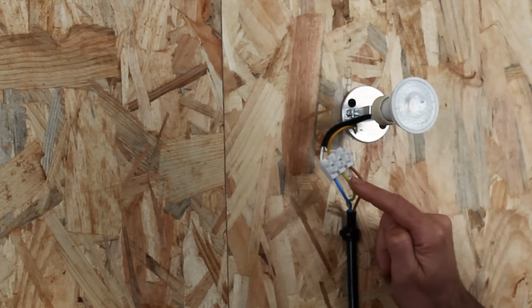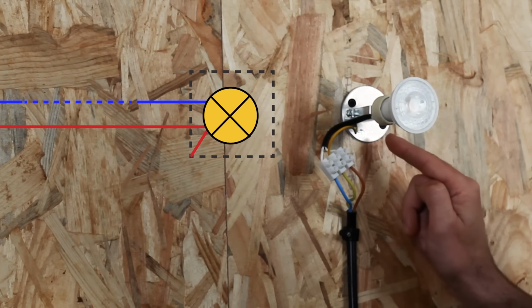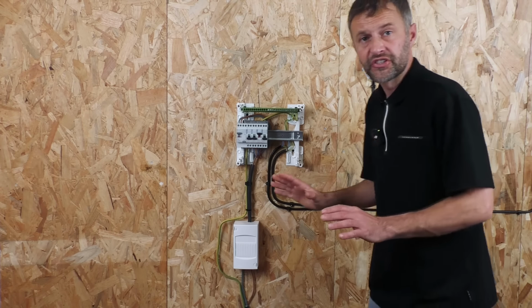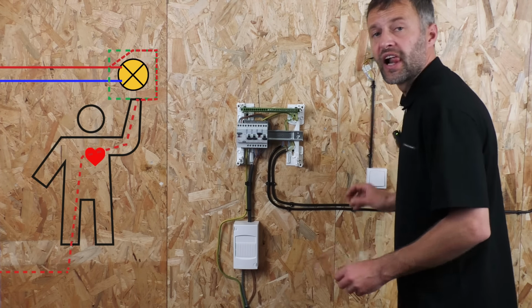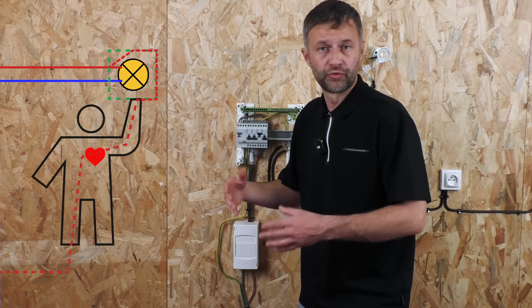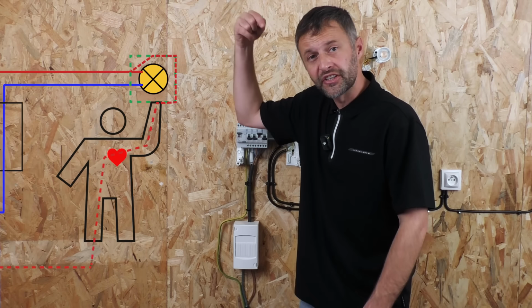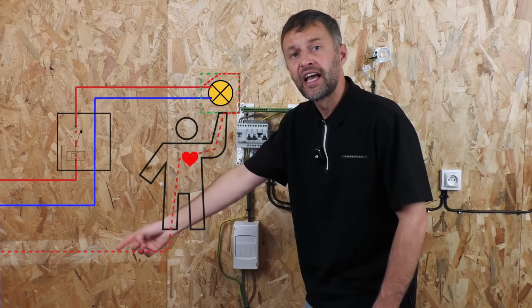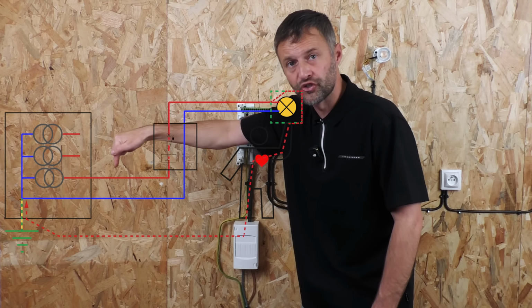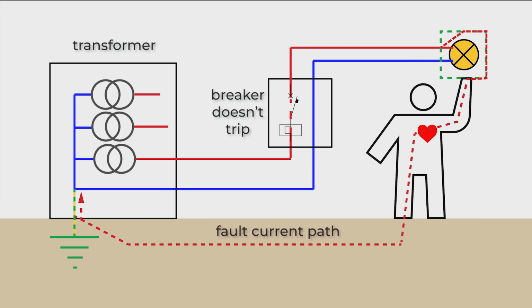If the earth wire is not connected to the metal housing and a live wire accidentally touches it, nothing may happen at first until you touch the metal yourself. And if you're standing on a wet floor or outside barefoot or wearing poor footwear, now this fault current can travel through you, through the soil and back to neutral at the transformer side, because neutral at the transformer side is connected to the soil, to the ground. Now, because both your body and the soil have much higher resistance than a copper wire, this fault current will not be high enough to trip the circuit breaker, but it may be high enough to stop your heart, so this is a very dangerous situation.